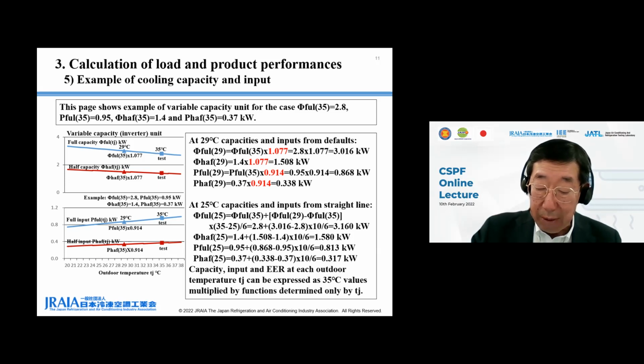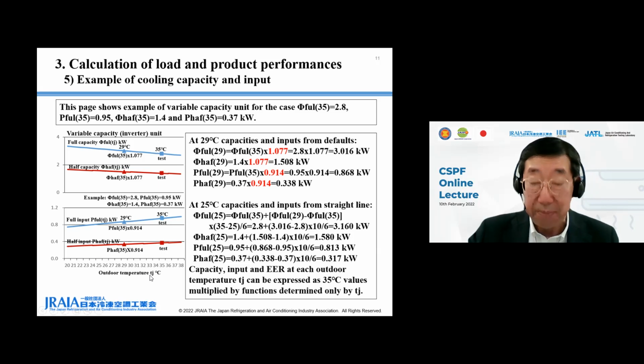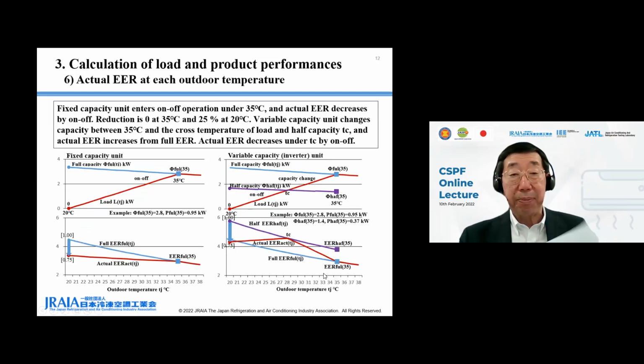ISO T1 bin hours exist from 21 to 35 degrees C. Full and half capacity, inputs and EERs at each Tj from 21 to 35 degrees C can be calculated only from 35 degrees C value and outdoor temperature Tj. Next, please.